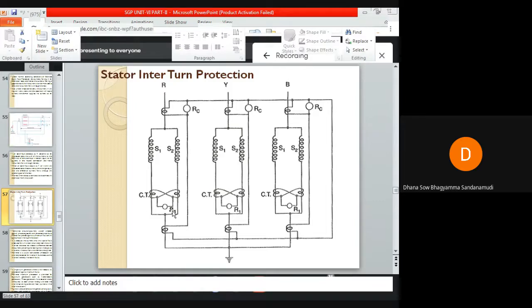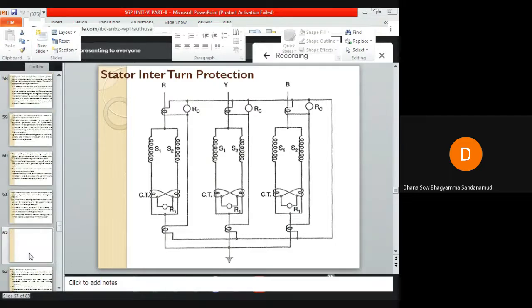Now if a fault occurs, it may be a short circuit between these two windings, S1 and S2. The currents measured by the primaries of these two CTs will no longer be equal. Therefore, the currents induced in the secondaries will no longer be equal, so a differential current will flow through this R1. When the differential current reaches the preset value of the relay, the relay will be energized, the trip circuit is closed, and the circuit breaker will open. So this is about stator interturn fault protection.